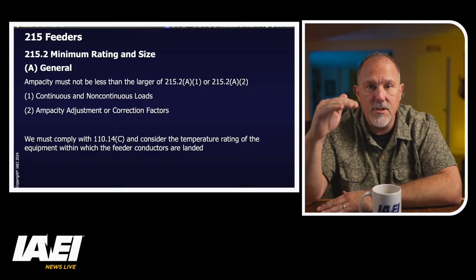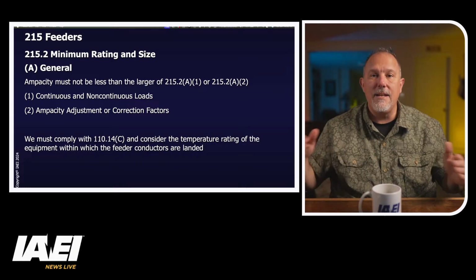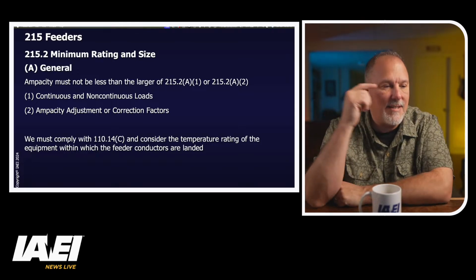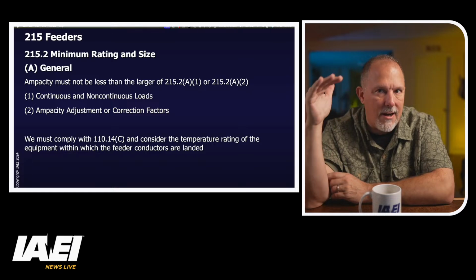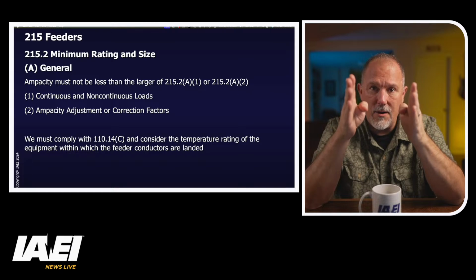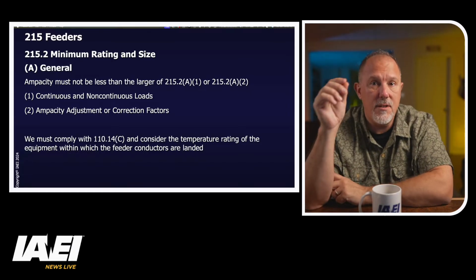Now I said that my largest was 175. In this case, if I'm landing in equipment that's 75 degrees C rated, I use the exact same table. I ignore the insulation ratings at the top. So don't get yourself bogged down; you're using this same table for a different reason. You're using this table to satisfy 110.14, the terminations. And if I am in 75 degrees C equipment, I'm going to look at the 75 degrees C column, and I at least have to have 175 amps. And it just so happens that because I was at 175 amps and I picked a 2-aught conductor, which is good for 195 amps, in the 75 degrees C column, it's good for 175 amps. So my conductor does not have to change.